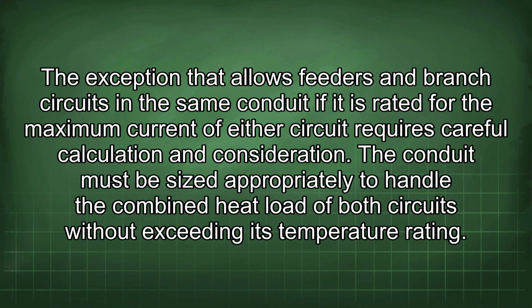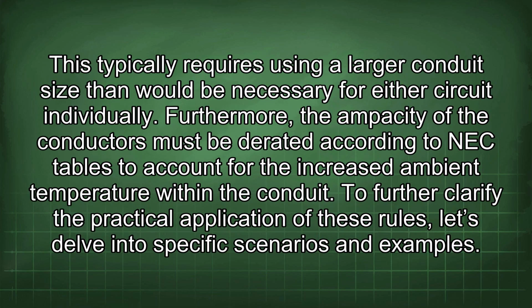The conduit must be sized appropriately to handle the combined heat load of both circuits without exceeding its temperature rating. This typically requires using a larger conduit size than would be necessary for either circuit individually. Furthermore, the ampacity of the conductors must be derated according to NEC tables to account for the increased ambient temperature within the conduit. To further clarify the practical application of these rules, let's delve into specific scenarios and examples.